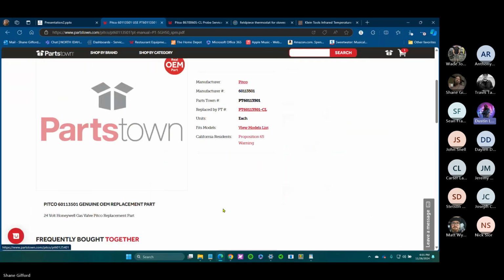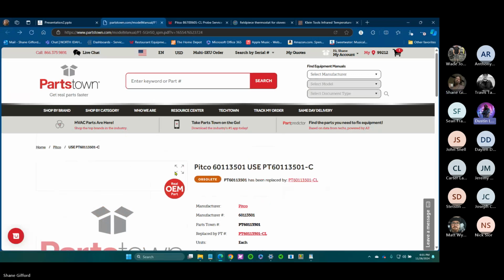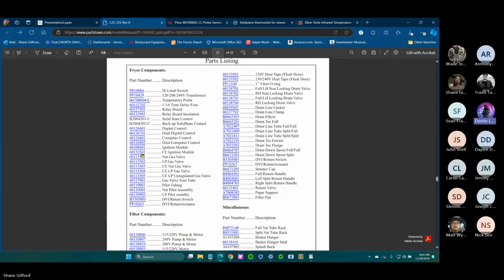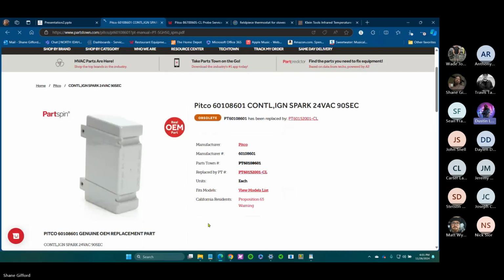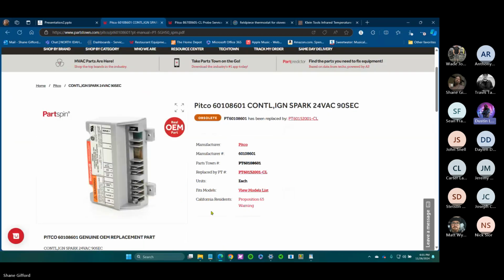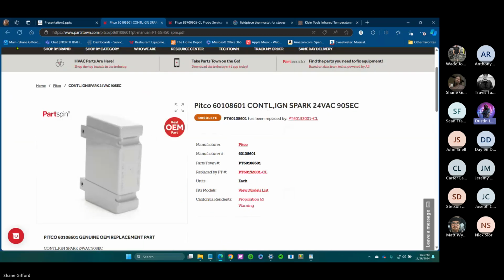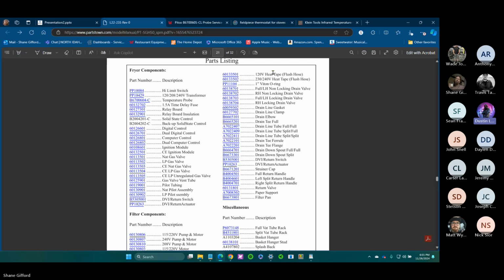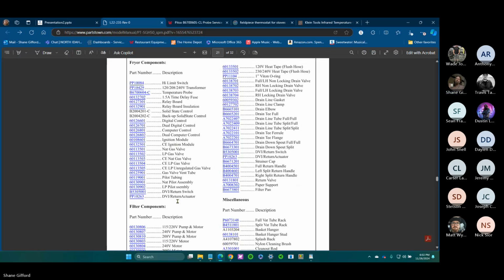And like Shane said, everything's connected to the main for the building. And it was in the middle of winter. It turned out that every time the rooftop called for heat, it stole all the gas and there wasn't enough gas for the fryer. It ended up being a main regulator for the building that was the issue. So don't ever go based off of just, I hooked up, it's at 4 inches of water column or whatever, like everything's good. Watch the gas pressure as it goes through its sequence.